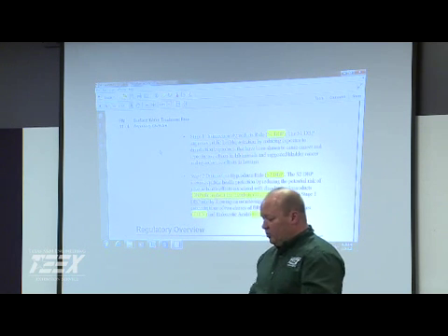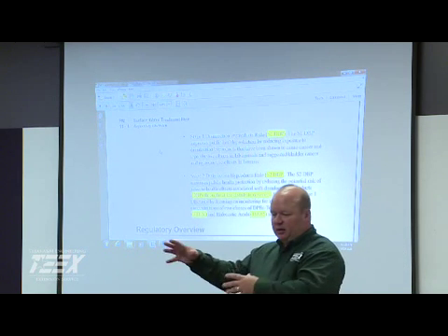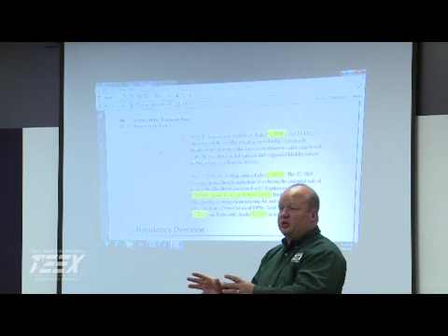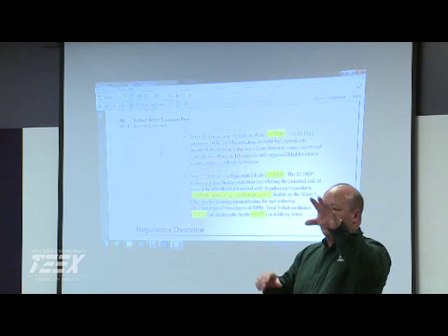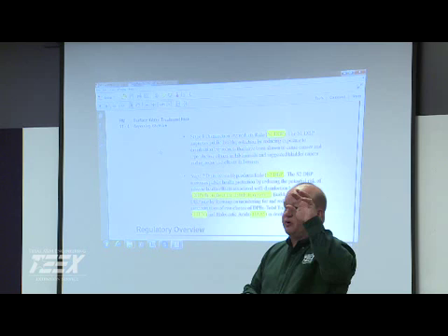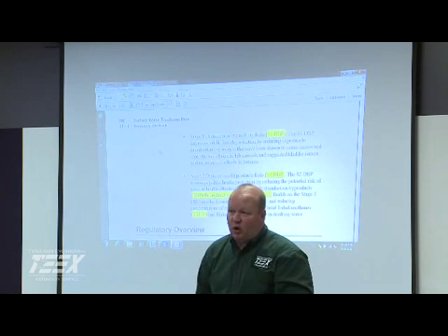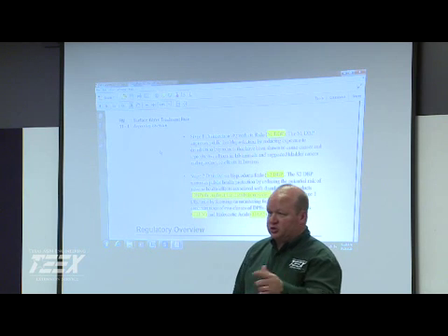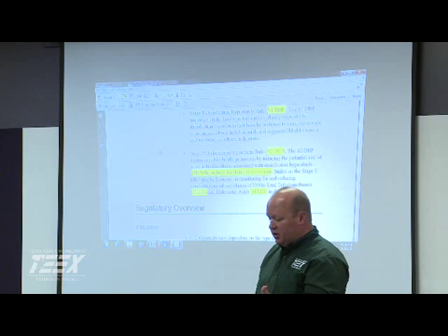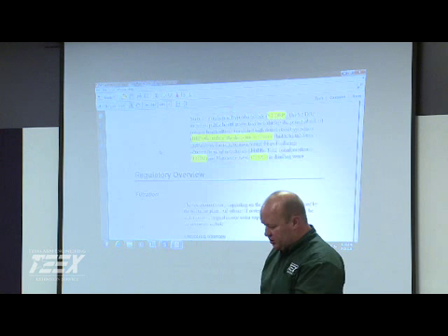And so then we not only started looking at it in the plant and in the distribution system, but then they started going from running annual averages into locational. So it used to be easy if you had a hot spot over here, it would average out pretty good with everything else. Now, if this is the hot spot, you have to deal with your hot spot. And that gets into a lot of your water age. You start looking at your disinfection processes, your TOCs, and how all that is going to affect it. And then the ones that we're really looking at are trihalomethanes and the haloacetic acids.